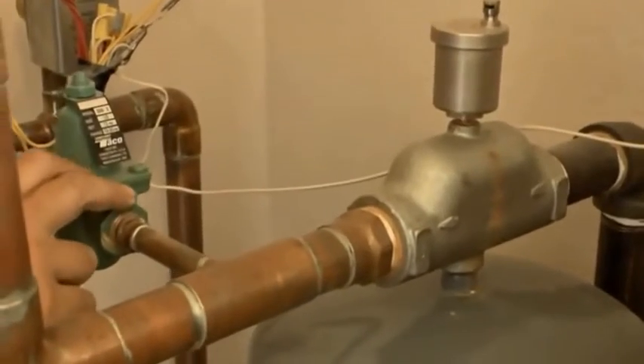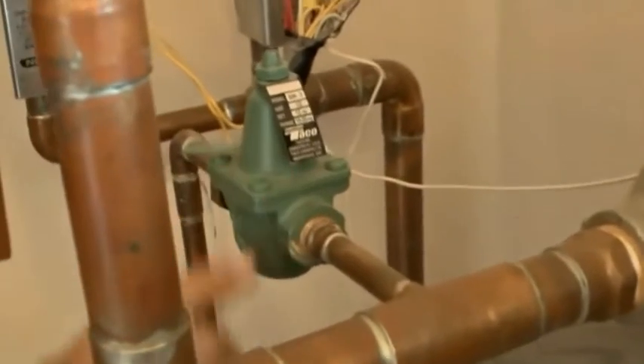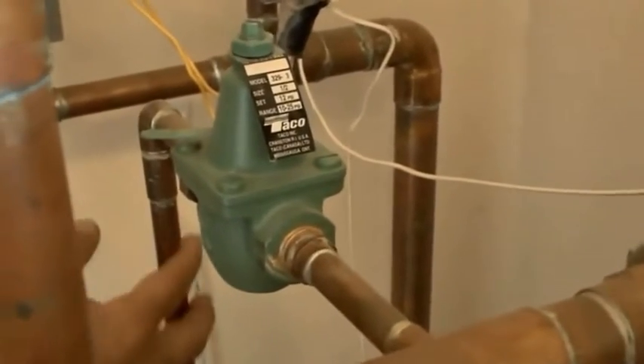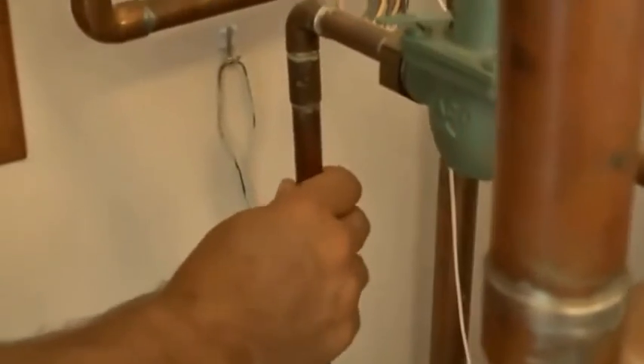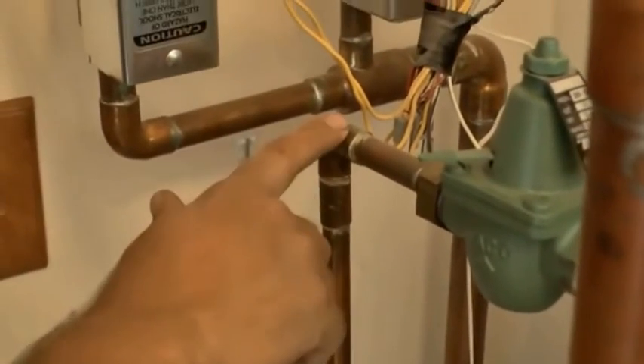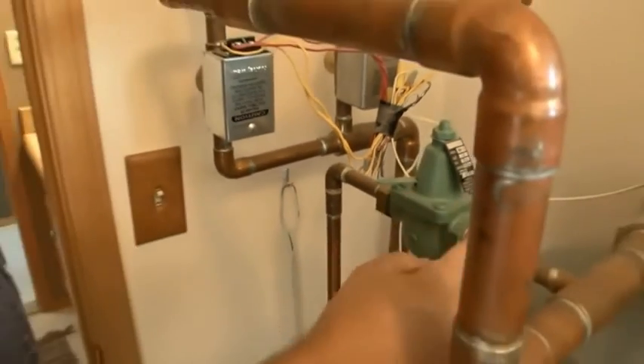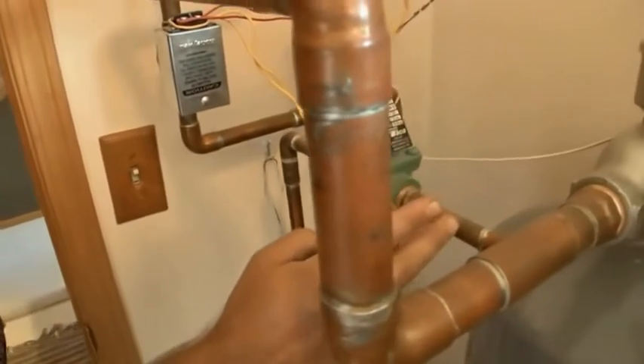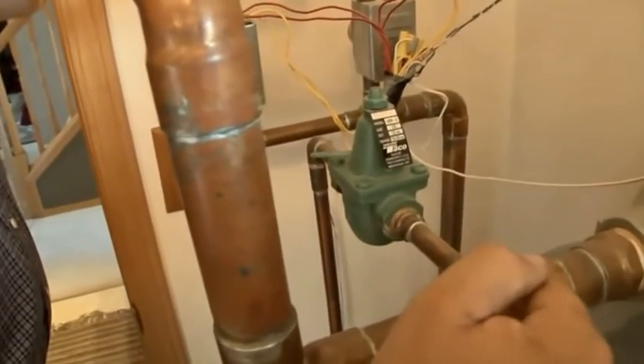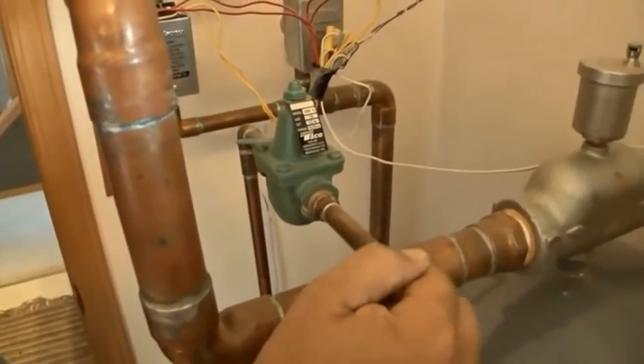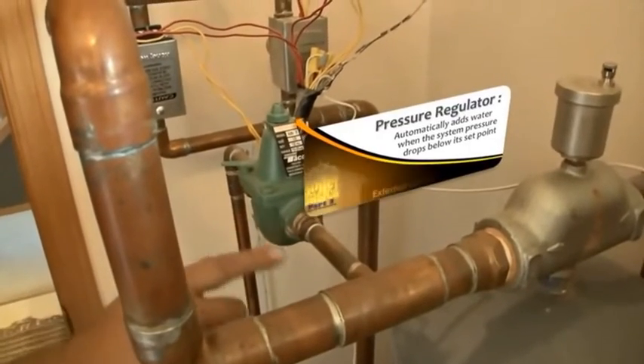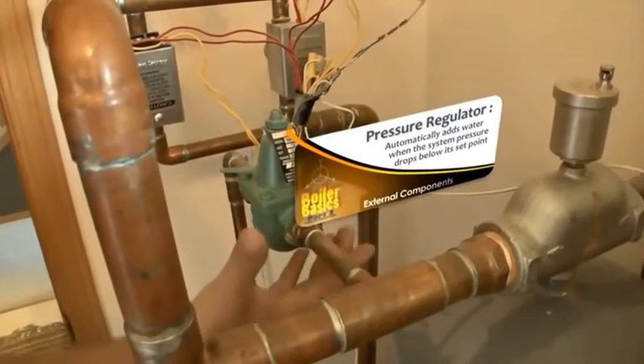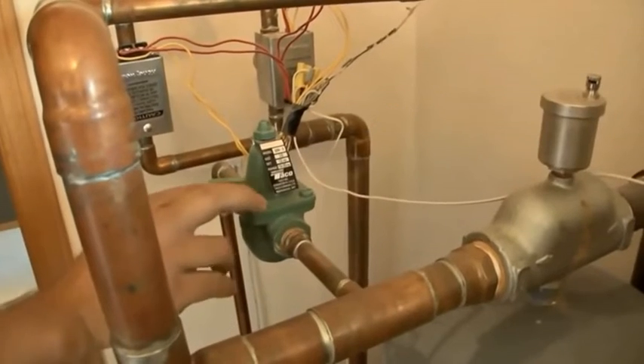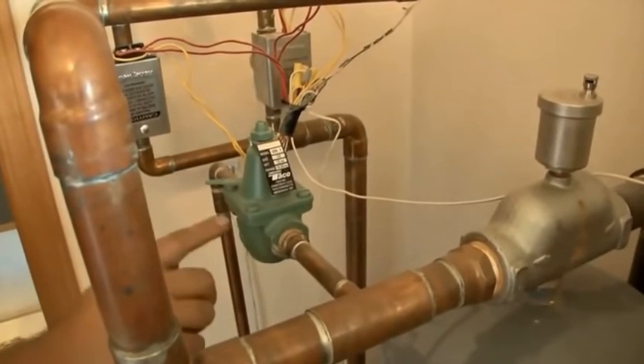This component over here is the pressure regulator. This is our house pressure, which typically is 60, 75 psi on this side. It reduces the pressure over to this side to 12 psi. So anytime the water pressure drops below 12 psi on this side, this automatically adds some water. This is a closed system, so it really is a rare occurrence when that does happen.